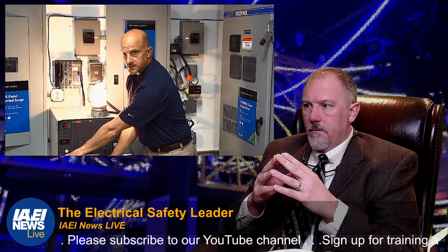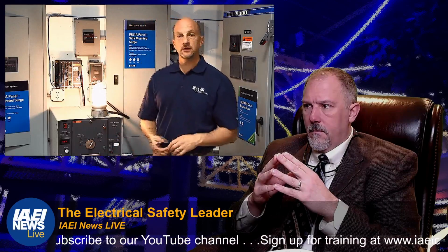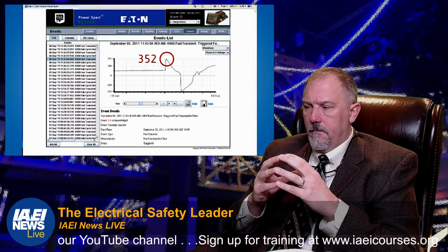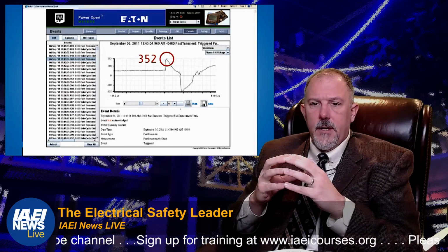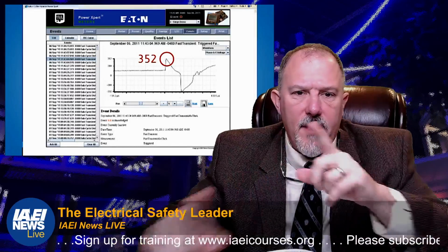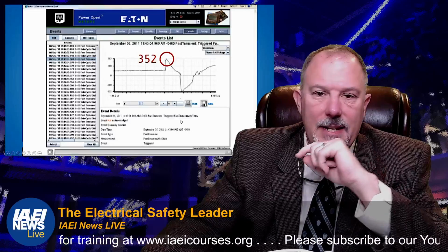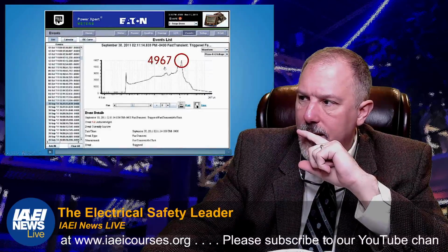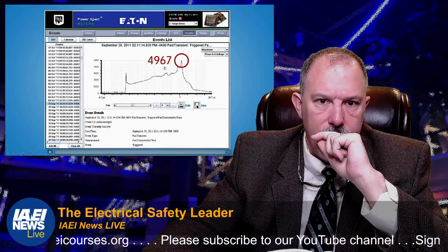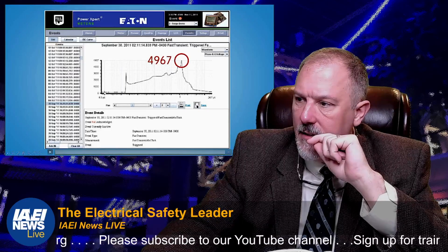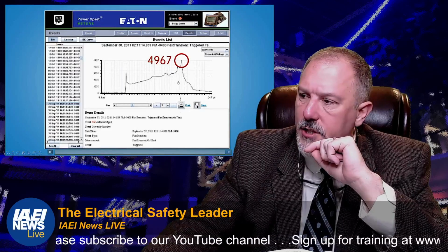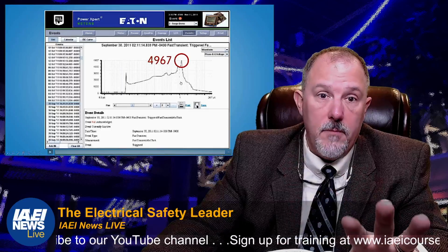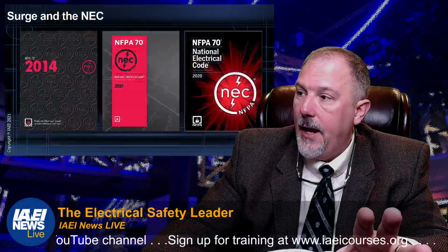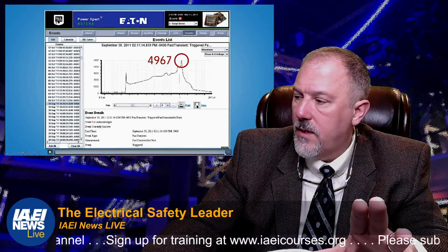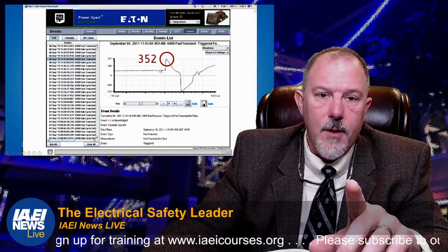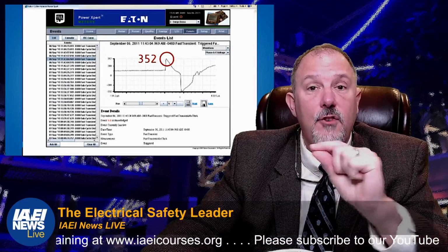With surge protection, the voltage gets clamped to 352 volts, protecting the load. Remember that first peak, that first transient that he showed was 4967. Okay, this is your trace of the voltage that light bulb basically saw. And what the surge protective device did was limit it to only 352 volts.